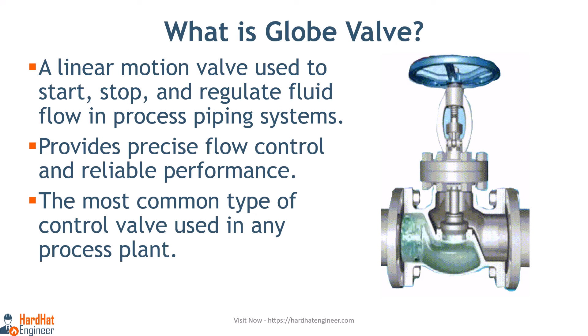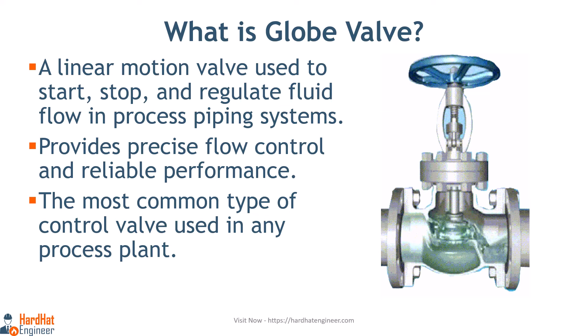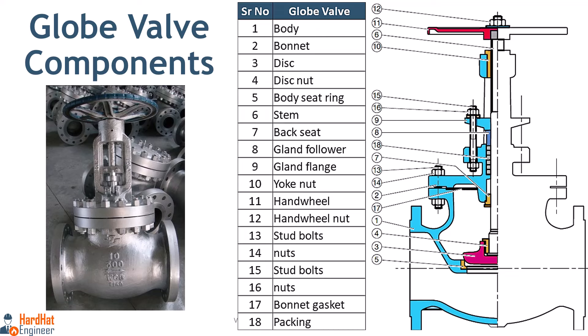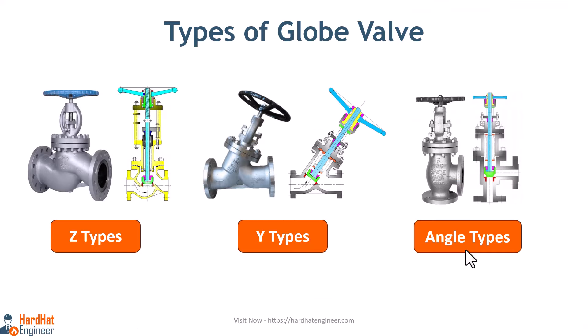This characteristic provides the globe valve good throttling ability required for regulating flow. Leakage from the globe valve seat is less compared to the gate valve, mainly due to right-angle contact between the disc and seat ring, which allows a tighter seal. In the valve cross section you can see the key components; the valve body shape is globular compared to a gate valve, which makes it easier to identify.